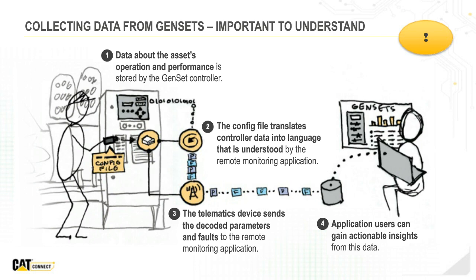So the first thing is you've got to look at what is the data stored in the genset controller that's critical information. What we need to do then is create what we call a configuration file, which translates that data - however the controller manufacturer or software provider has written that software - into a language that can be read by the remote monitoring application. Think of this step two as a translator. Your genset controller is speaking Spanish, and your remote application is speaking French. This box here, number two, is basically translating that from Spanish to French.